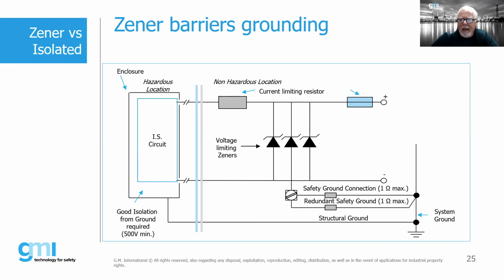The reason why we have a redundant ground, as good engineering practice, is that periodically we're supposed to check whether this ground loop still has 1 ohm of resistance or less. The only way we can check that is to disconnect it from the barrier, because obviously if the barrier is providing protection into the hazardous area, we don't want to do that test while the barrier is connected to that intrinsically safe earth. So we have a redundant safety ground. It's not uncommon. This is not a requirement within the standards, but it's good recommended engineering practice.